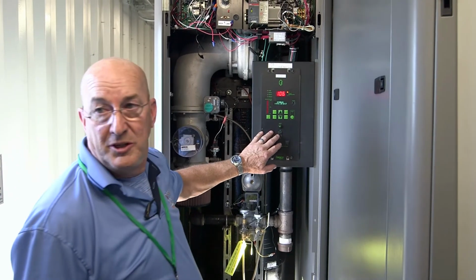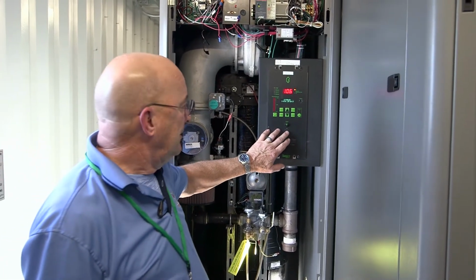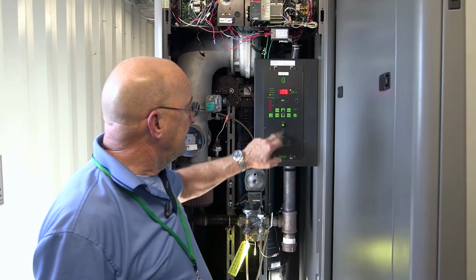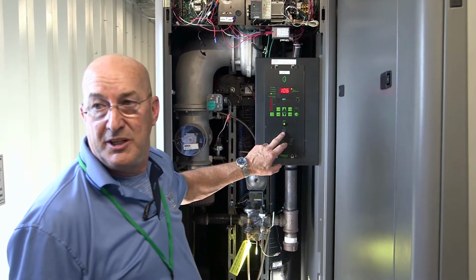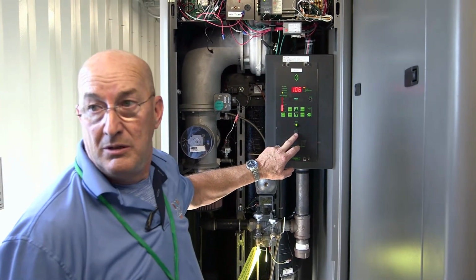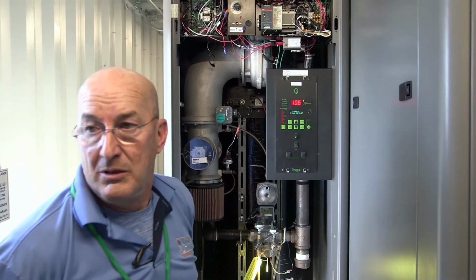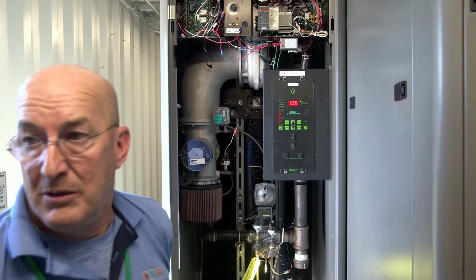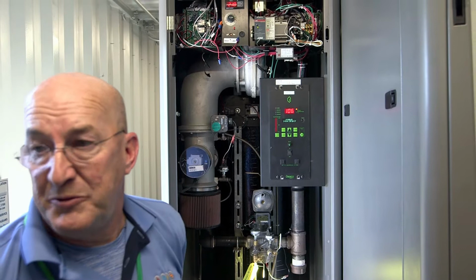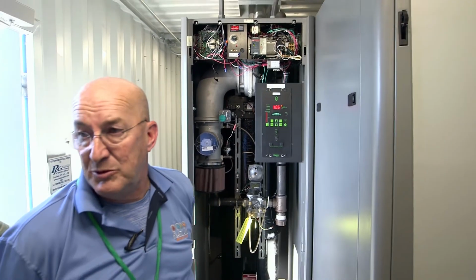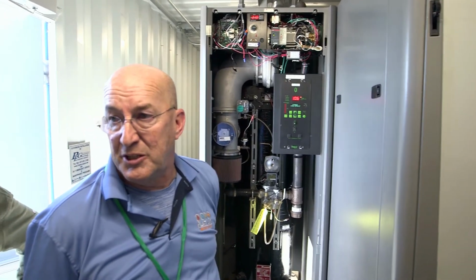This is the switch for the on-off. It's off right now. You see when it goes on, the light turns green. It tells you, hey, I'm ready to go. Now, if we have a problem with that, should I hit that off switch or just leave it alone? If it goes off on the manual reset, just leave it off on the manual reset. Okay. It's not going to come on.